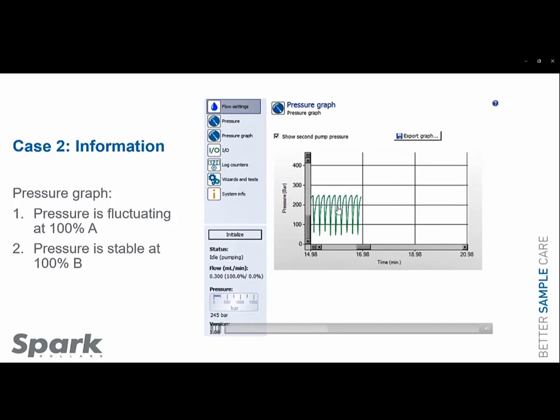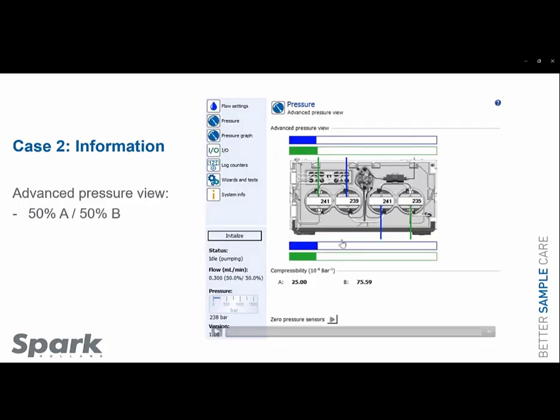Let's see how pump B is doing. So we are now at 100% B. Now this is nice and stable. So this is good. So B is good. The problem is A. Let's see what it does when we do 50-50 and how the pressure sensors, which are installed and integrated into all 4 pump heads, are giving an actual pressure. Running 50-50% AB. This is the pump pressure, the system pressure.